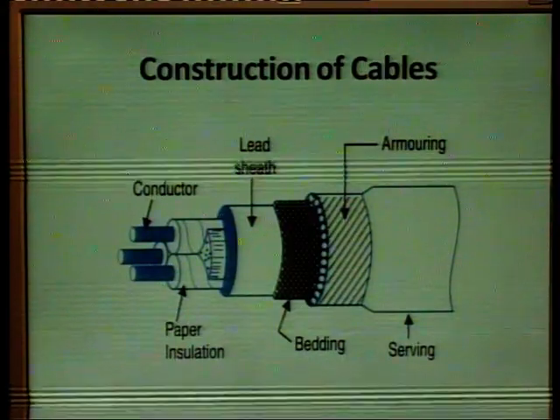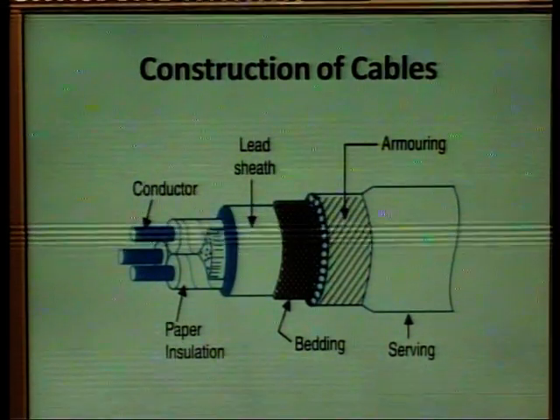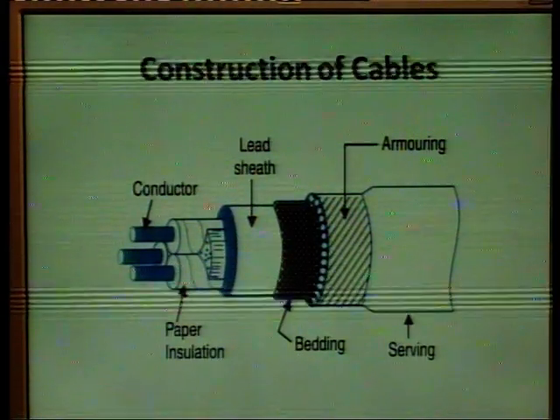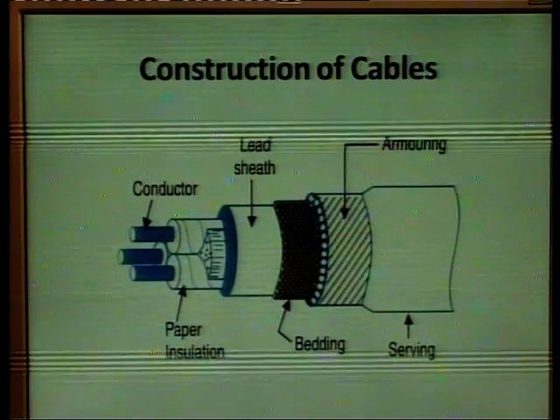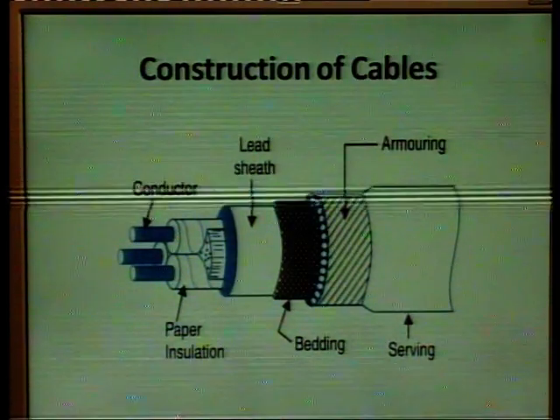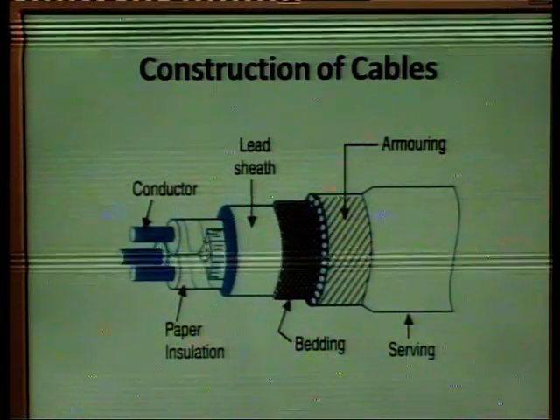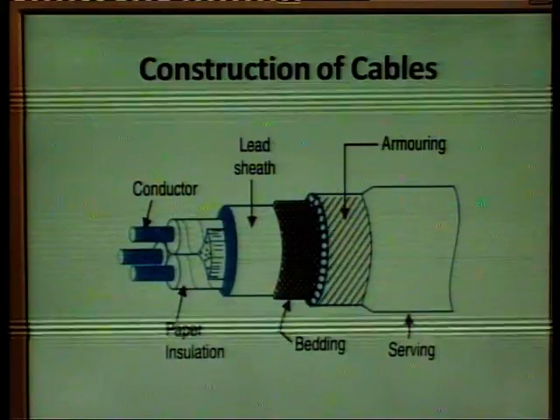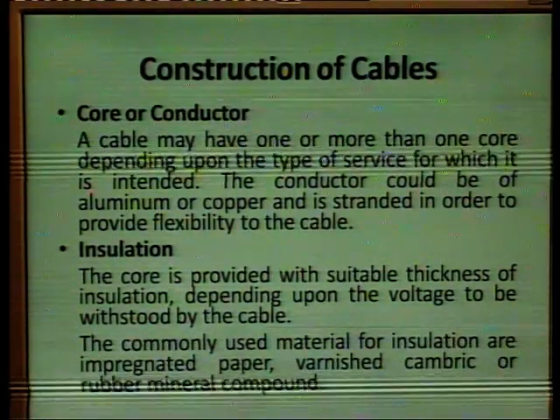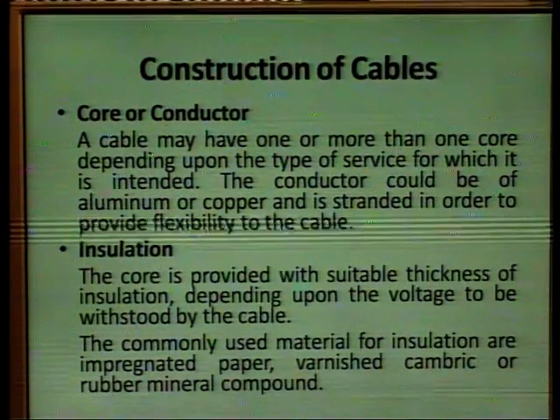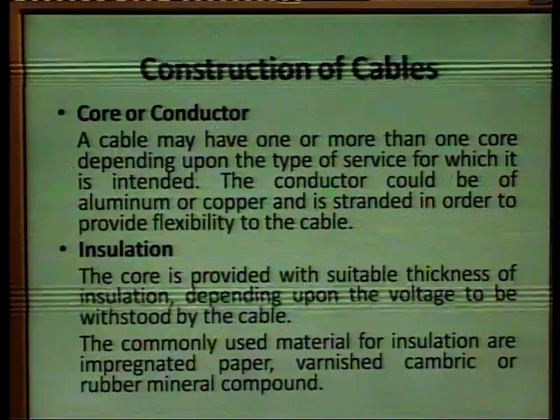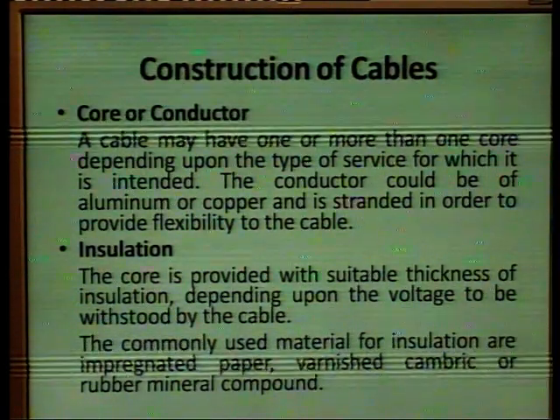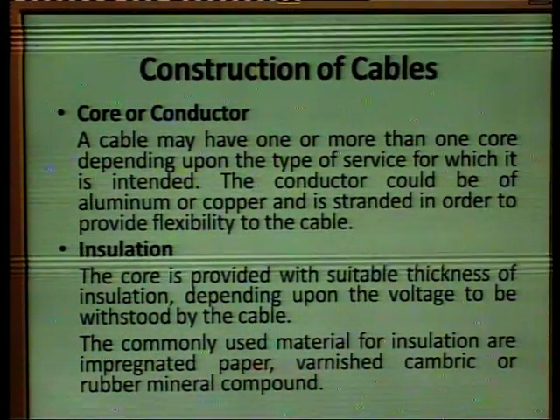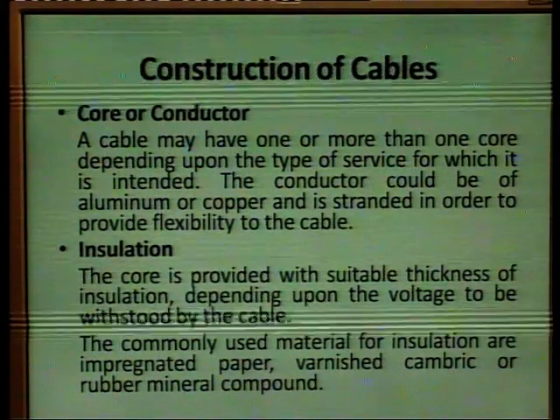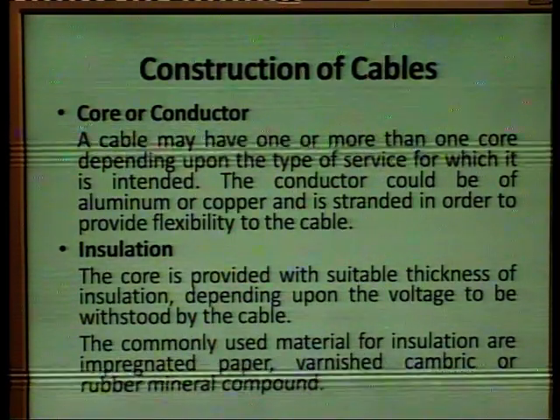On the outermost part we have the serving, then armoring, bedding, the lead sheath, paper insulation, and the conductors. We will discuss them in detail. The core or conductor: a cable may have one or more than one core, depending upon the type of service for which we intend it. The conductor could be of aluminium or copper, and it must be stranded in order to provide flexibility to the cable.